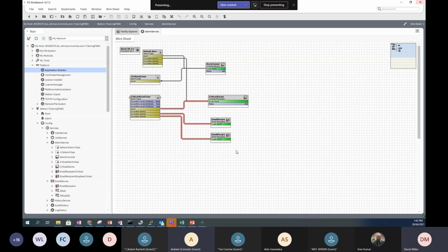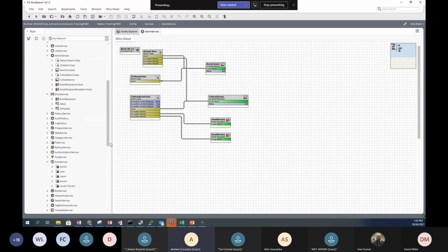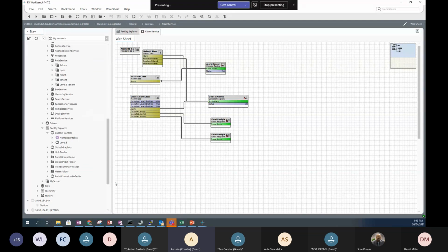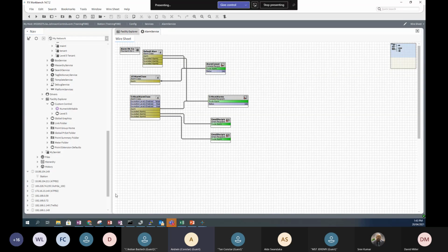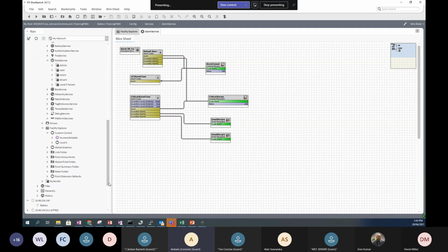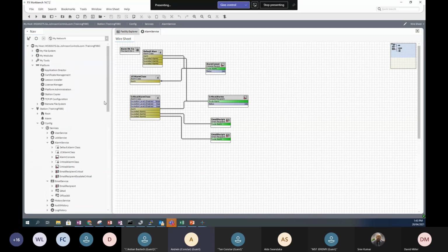So you're using, so you've set up the alarms route back on the FX server itself, where we acknowledge it. The thing is, it seems it can't synchronize correctly. Sometimes there's leftover alarms on the FX80 itself, even though from the FX server interface we see the alarm is clear after we acknowledge it. But the alarm is still left over at the FX80 level.